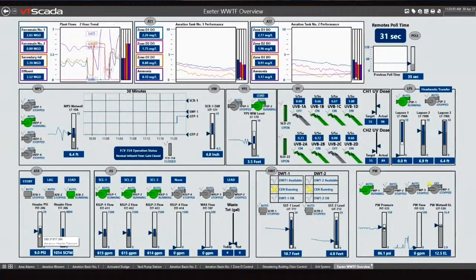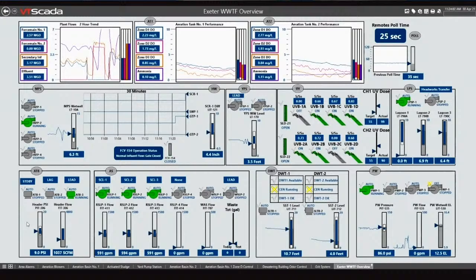Another thing I was mentioning is putting this data in context. Right down here, what we have is, again, we have the numerical value, but we also have this little arrow and this gray bar that's showing the current value, but we have some other information around it showing the blue bar that's within an acceptable range. And then outside of the white bars, those are our alarm limits. So you can quickly look at this and say, hey, I'm right in the middle of the blue bar. I must be doing pretty well with that process.